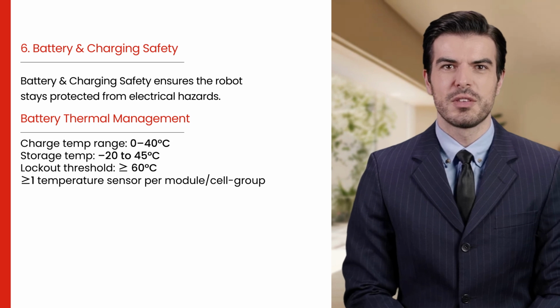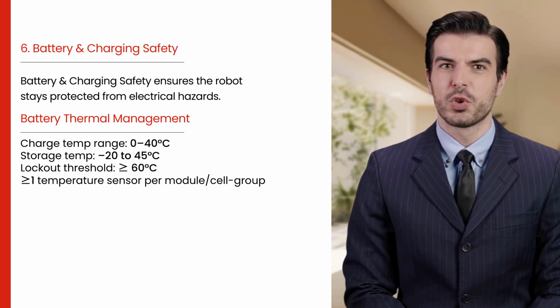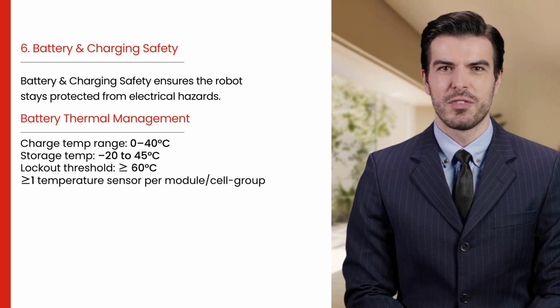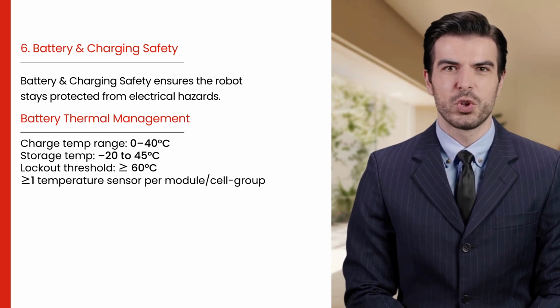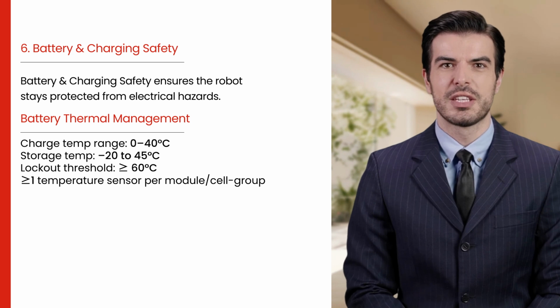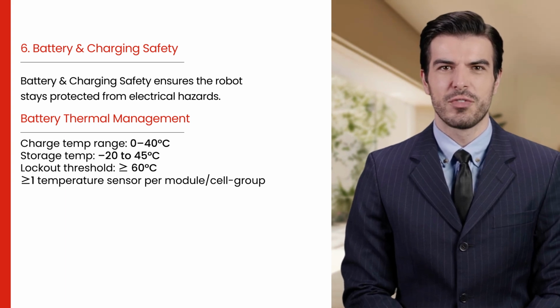The battery system must stay within safe temperatures at all times. Charging must occur between 0 to 40 degrees Celsius, storage between -20 to 45 degrees Celsius, and the system should trigger lockout if temperatures reach 60 degrees Celsius or above. Every module or cell group must include temperature sensors to ensure early detection of overheating.